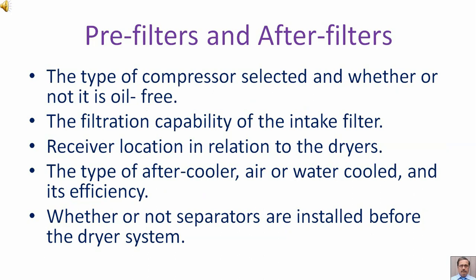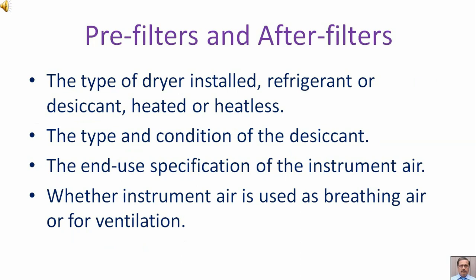Factors to consider include: the type of compressor selected and whether or not it is oil-free; the filtration capability of the intake filter; receiver location in relation to the dryers; the type of after-cooler (air or water cooled) and its efficiency; whether or not separators are installed before the dryer system; the type of dryer installed (refrigerant or desiccant, heated or heatless); the type and condition of the desiccant; the end-use specification of the instrument air; and whether instrument air is used as breathing air or for ventilation.